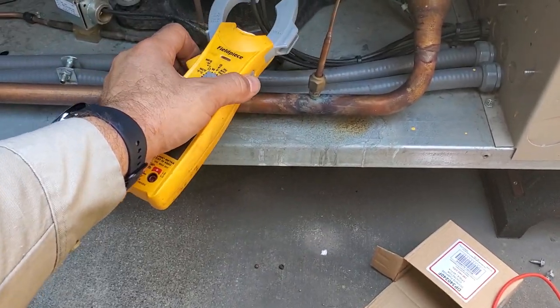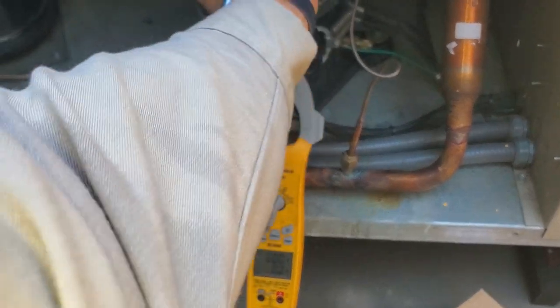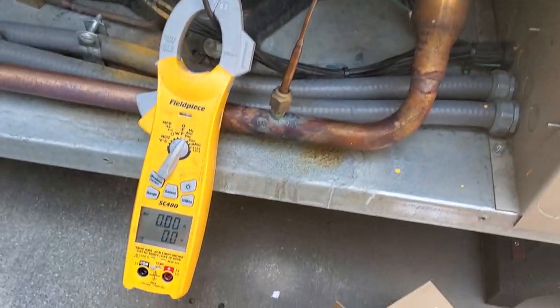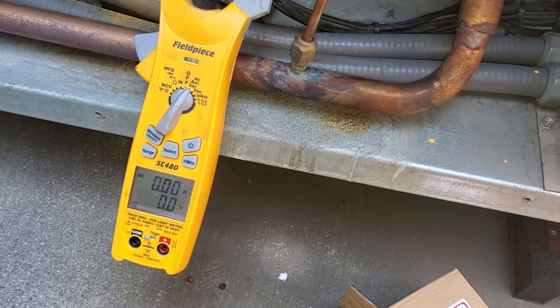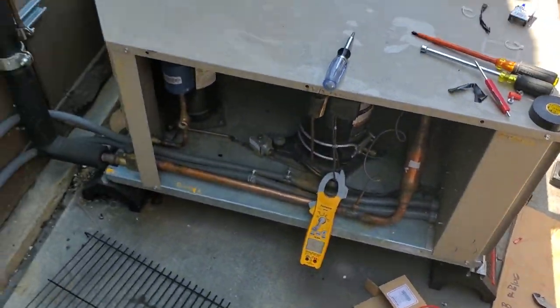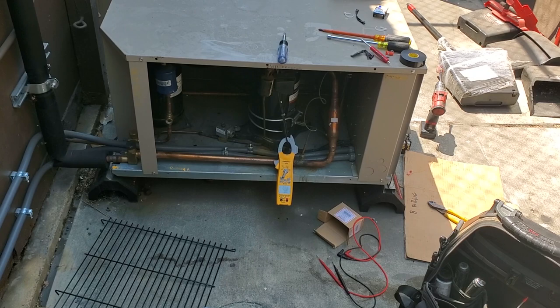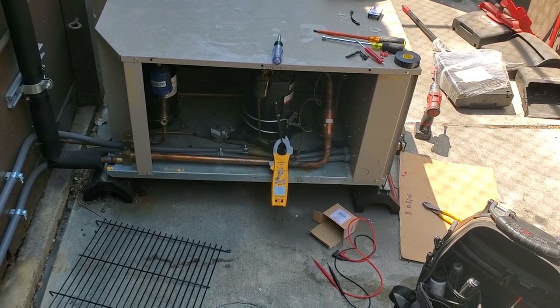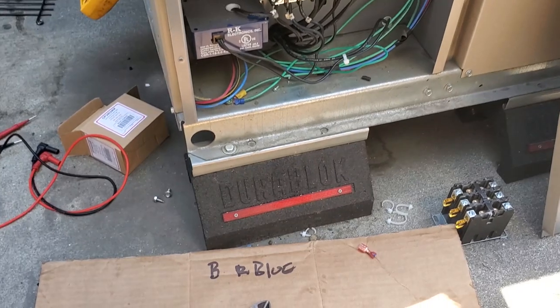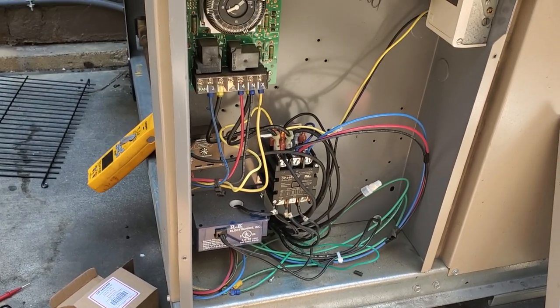I'm going to have to turn this thing on again and test to see what the heck is going on. Let's get an amp clamp on there. I better put this electrical cover back on because we don't know what's going to happen here. Locked rotor is 88. Let's see if this thing makes this awful sound again. Compressor sounds like dirt. Sounds like it's running backwards. But I hooked it up the same — black, red, blue. I'm really dumbfounded right now.